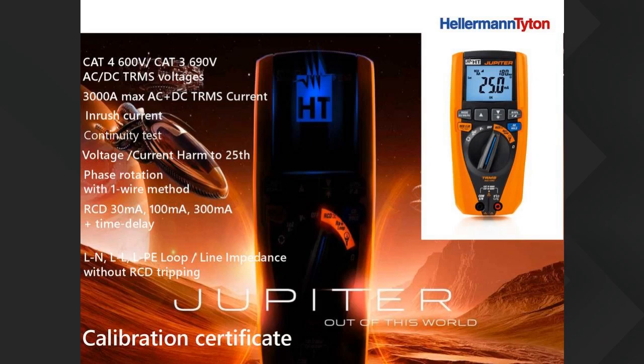So to explain that, basically, is when you're measuring an earth leakage in a domestic unit of 30 milliamps, a lot of times you measure the earth leakage, and when it reaches a certain point, it has to trip, let's say on 25 milliamps. But it takes a little bit longer, let's say longer than half a second. If it takes that long, that meaning that earth leakage might be faulty. Even though it tripped, it just takes too long.